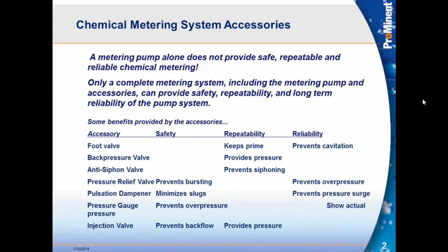Pressure relief, of course, that's a safety issue for us. So now the system may demand more pressure than what we have our back pressure valve set to. The pump will continue to pump, providing it's rated higher than what we have it set to. And then since the system is already above what we have the back pressure valve set to, we've achieved that pressure. The back pressure valve is open. We're pumping through it, and now we're achieving the pressure that the system demands. Well, we want to limit that. So now we've essentially established a minimum pressure that the pump is always going to see with the back pressure valve, and a maximum pressure that the pump is going to see with the pressure relief valve. So those are very critical things.